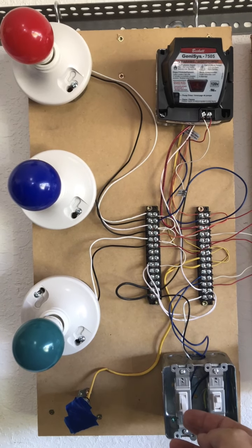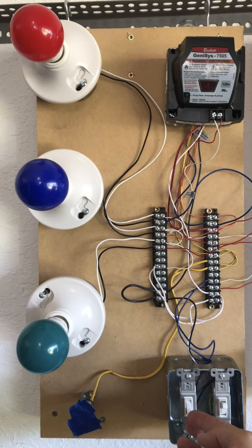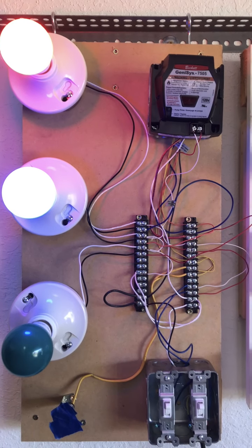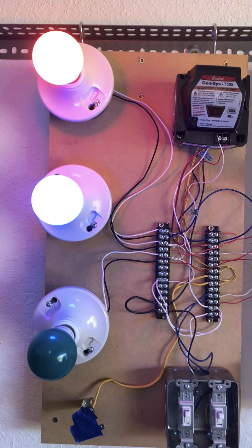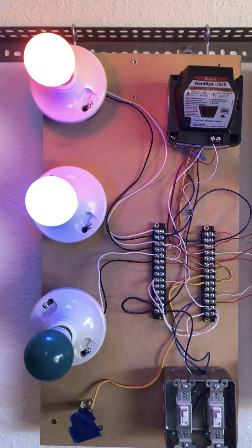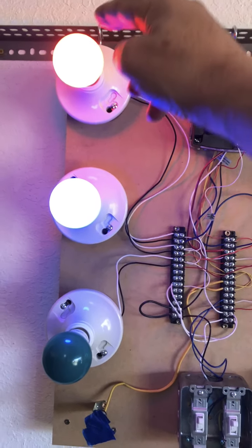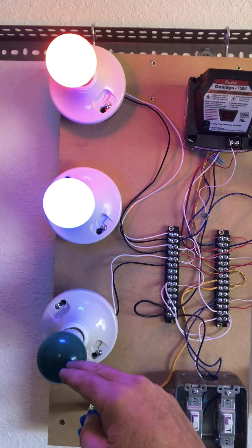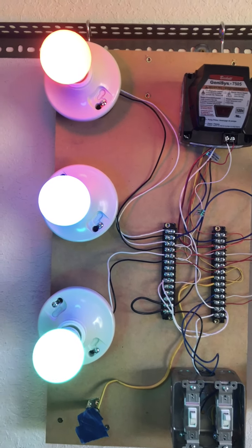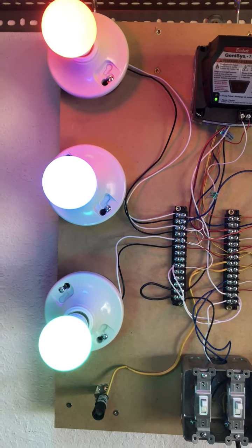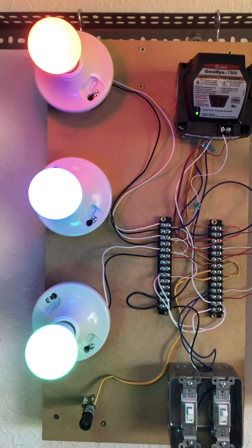Now when I close my thermostat, we turn on the burner motor and we turn on the igniter. Again, the burner motor is my center light, my igniter is my top light. Notice I haven't opened my oil valve solenoid yet. What I'm doing here is upping the pump pressure. Now the solenoid opens and we should see light on the CAD cell.